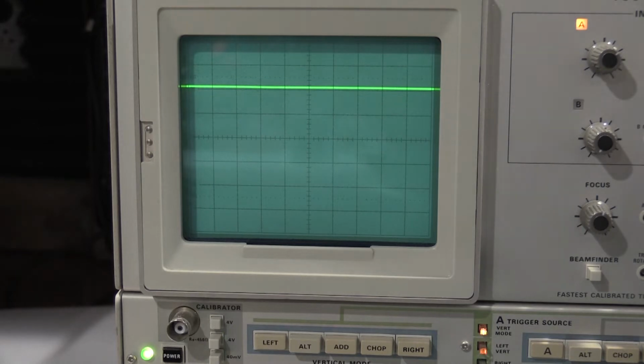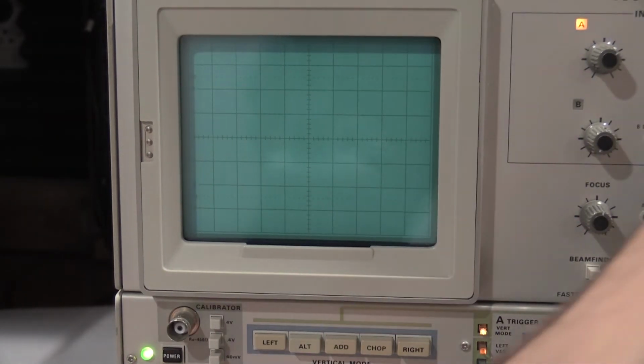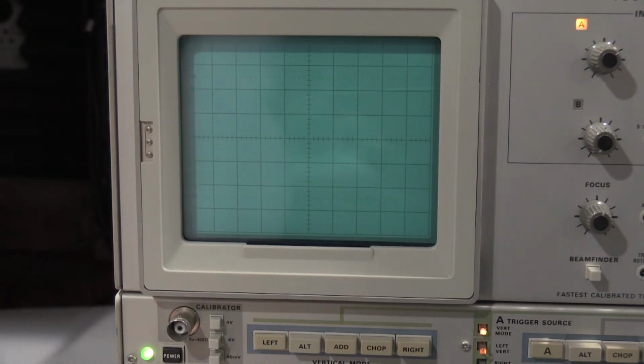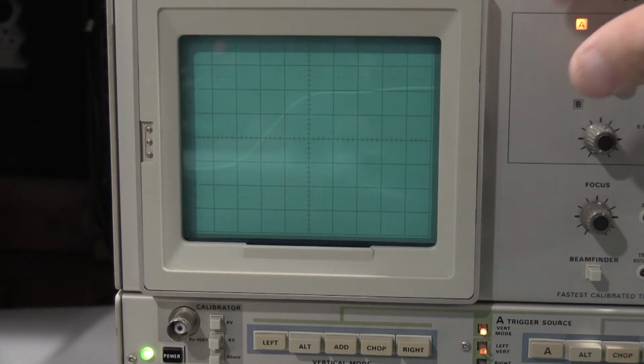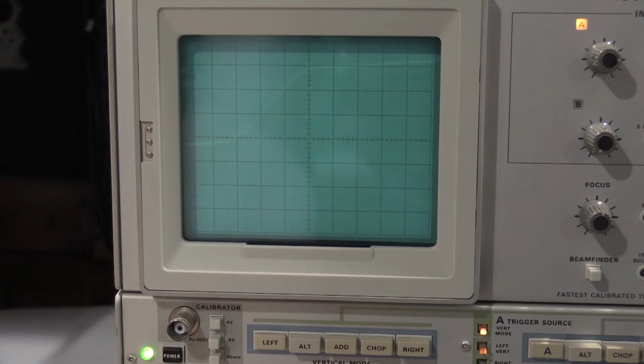Let's check as high as this will let us go on the fast fall. I have to pull the 10x out. There we go. Good there. High frequency compensation on these verticals is where you can gain or lose bandwidth. So spend some time in this section. In a worst case, I've had a scope, I think it was a 465 that I was working on, and the high frequency was out so much, my PG506 topped out.